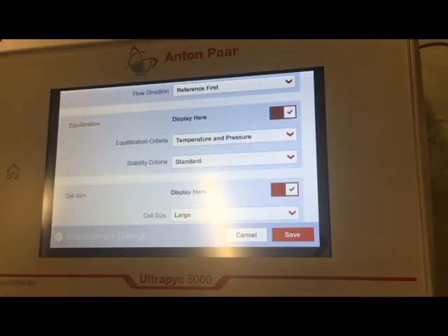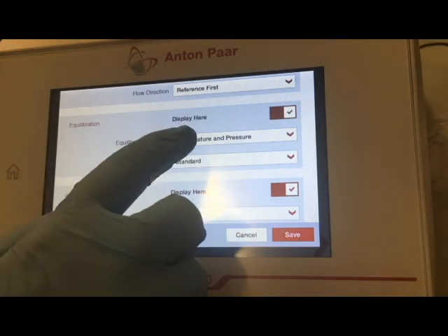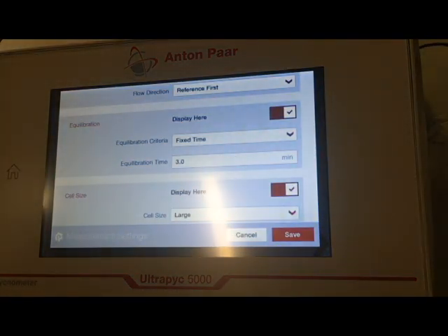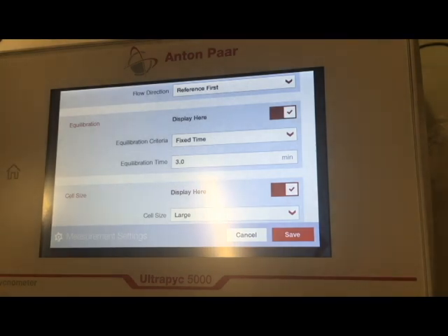Next is equilibration. There are 3 options for the equilibration criteria. We have fixed time, pressure, or temperature and pressure. Fixed time is going to be the fastest, which also means that it's the least precise of the 3 options. Fixed time means that it is going to take data values every 3 minutes throughout your test. So that means that one cycle will take 3 minutes.